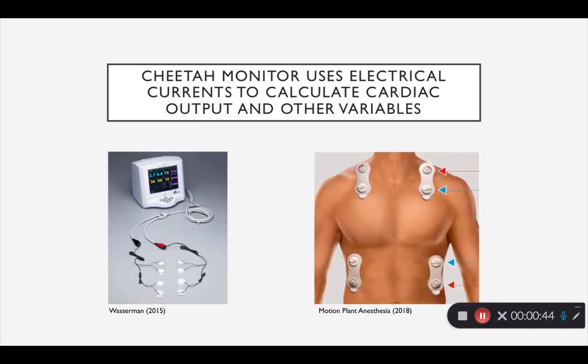Fortunately, the Cheetah Monitor is such a non-invasive device, and it works by attaching electrodes above and below the heart, as seen in this picture. By using the concept of bioimpedance — how different body tissues impede electrical current — it can measure fluid changes in the thoracic cavity to derive cardiac output and other important parameters.